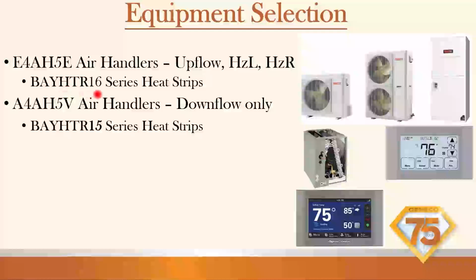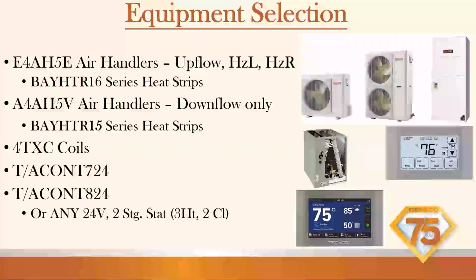The E4AH5E takes the BAYHEAT 16 series heat strip, so it is different than the A4AH5 for downflow only, which takes the BAYHEAT 15. So when you're ordering those, make sure that you have the right heat strip. 4TXC coils with the TXV, everybody knows that when you're brazing in this suction line right here, make sure that you take the TXV bulb off, because you can overheat that pretty easily and ruin the TXV. We see it quite a bit.